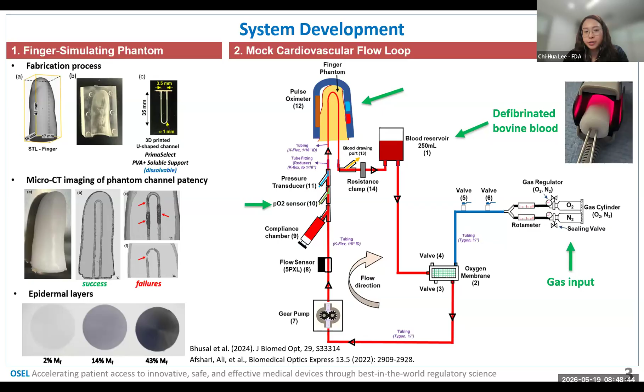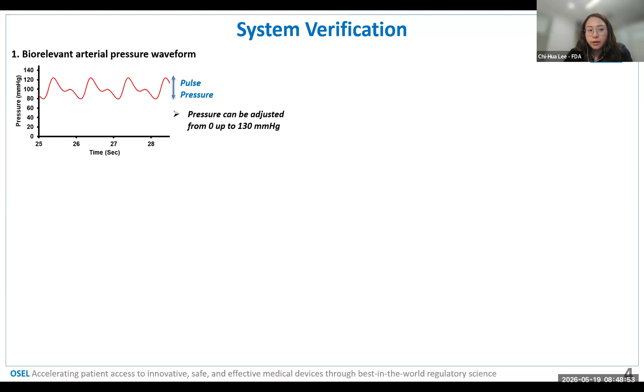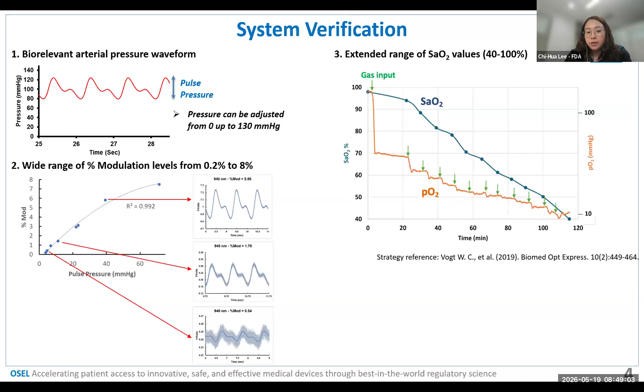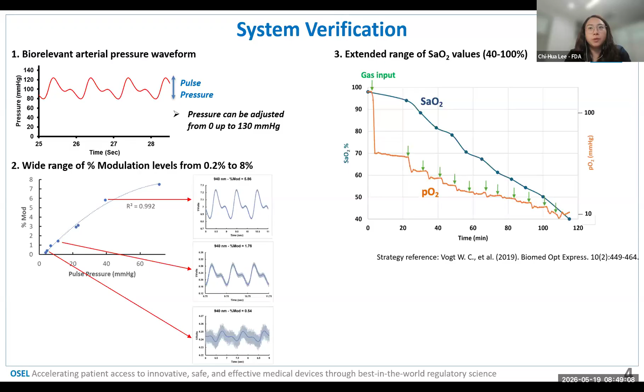First, we verified that our system is capable of, one, generating physiological pressure waveforms from 80 to 120 millimeters of mercury. And two, we were able to achieve a wide range of pulse modulation levels from 0.2 to 8%. And three, we were able to extend the range of oxygen saturations from 100% all the way down to 40%.